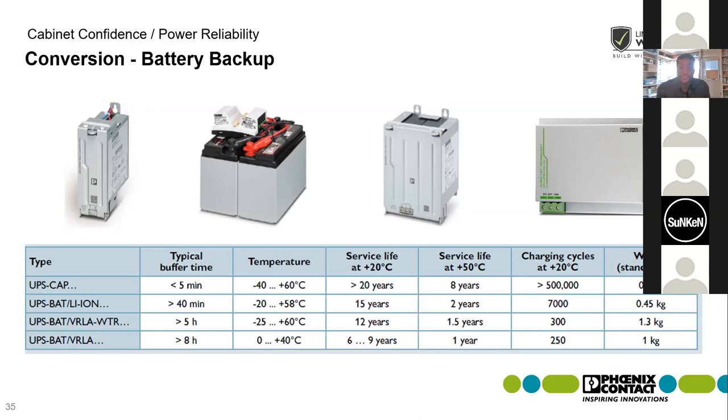The wide-temp VRLA goes from minus 25 up to 60 degrees C. One of the limitations in cabinet temperature ratings can be the batteries themselves, which is why we offer the wide temperature range option. These are maintenance-friendly energy storage units — the battery is easily accessible via a trap door on the front. They have quick-connection tabs on the front of the batteries. Once you disconnect the tabs, you can pull the battery right out and replace it — they're hot-swappable. Depending on size, they'll have panel mount tabs. The only exception is the 38 amp-hour version, which would have to go on a shelf or floor due to size.